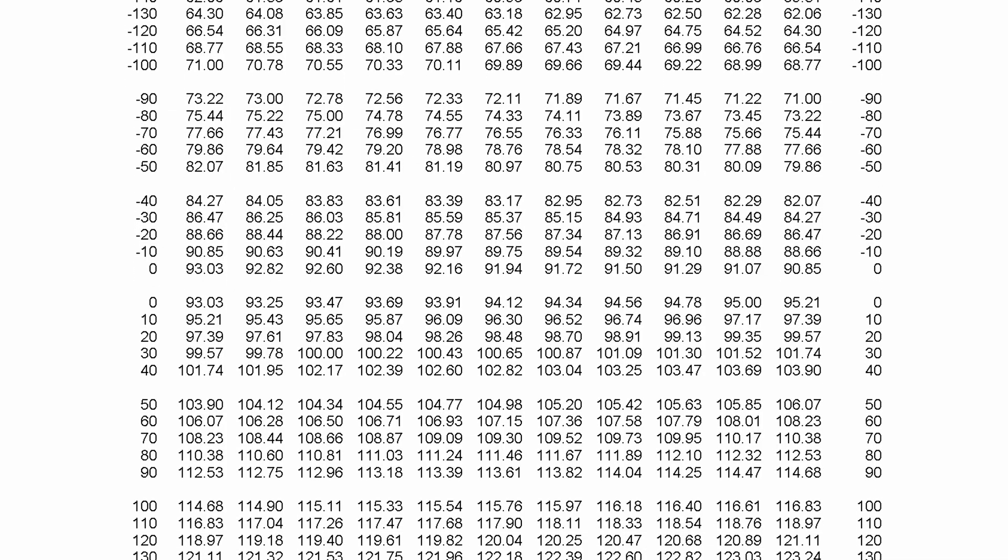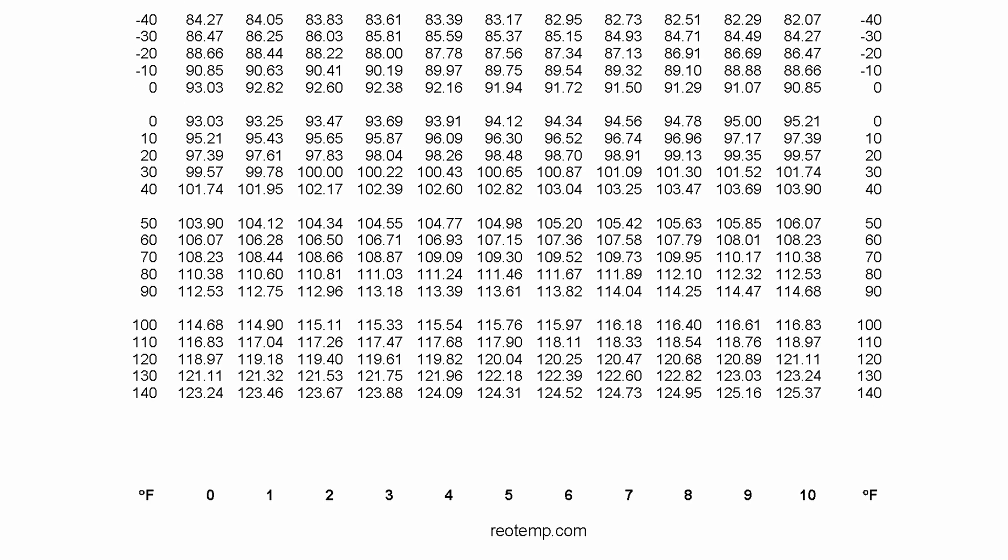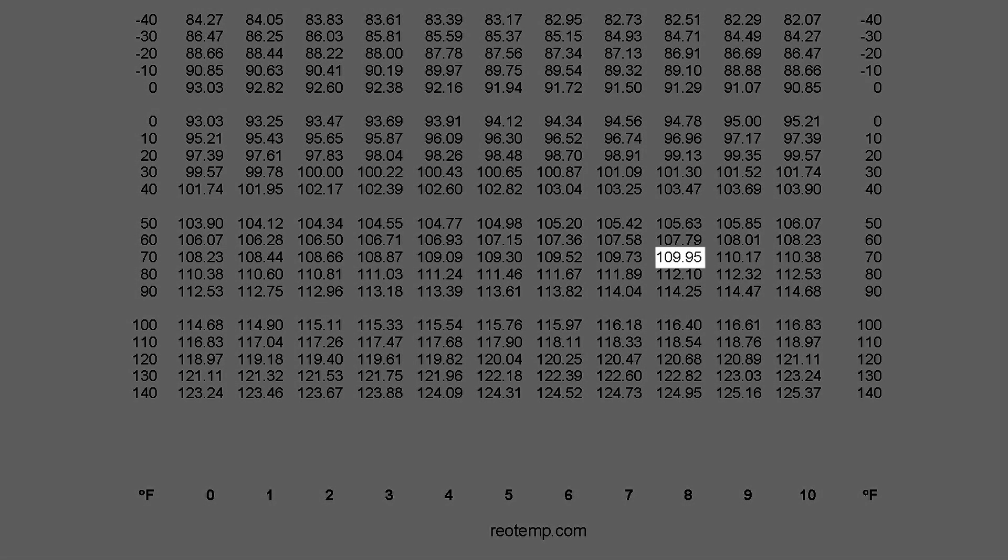First, use a lookup table to determine the expected resistance of the RTD based on the current room temperature. Here in San Diego, it's sunny and about 78 degrees out, so our expected resistance is about 109 ohms for a PT100/385 alpha RTD.